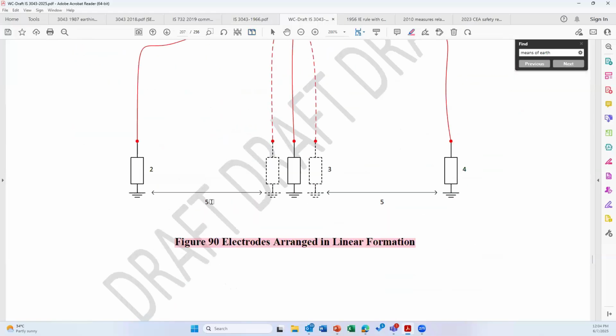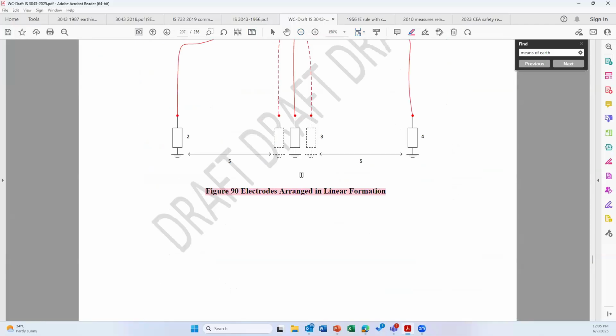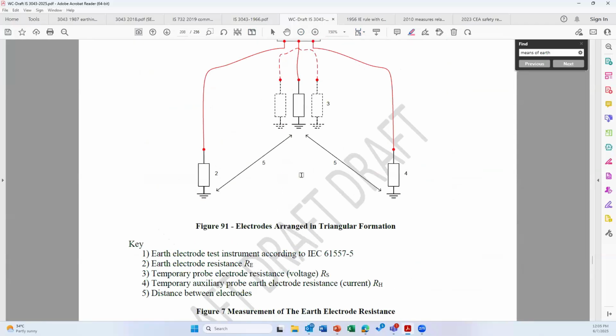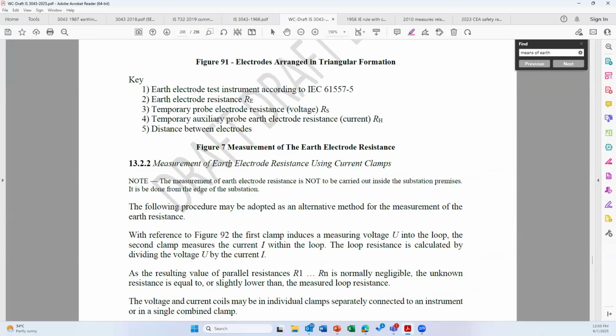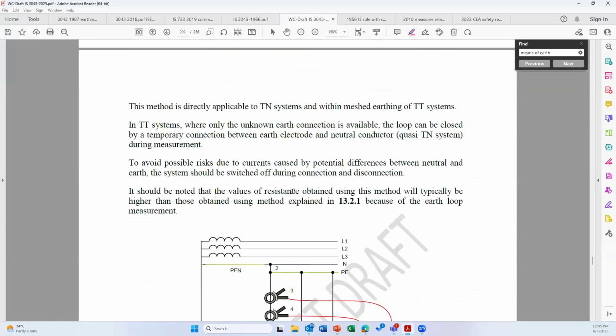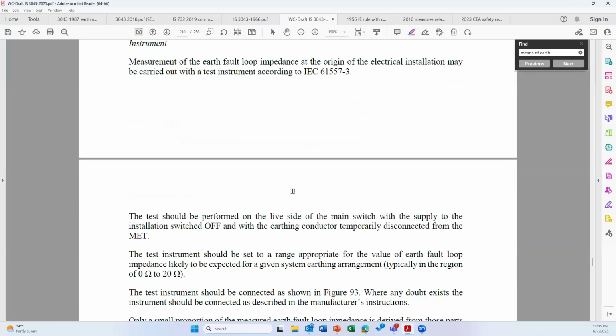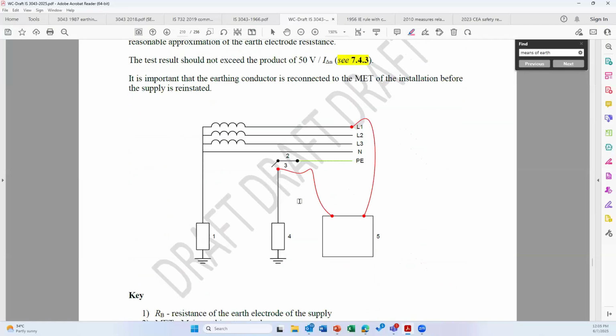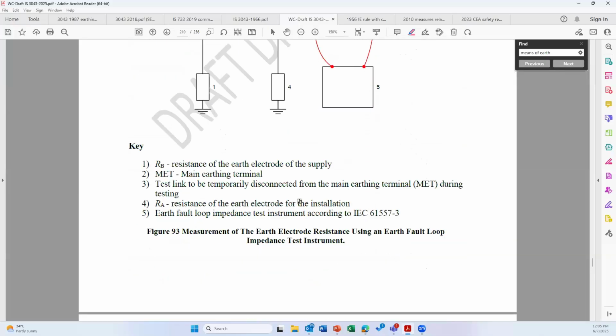Please note that earth electrode resistance measurement is not necessary always. It may be required if you go for a type A earth electrode for a lightning protection system. In other cases, it's not mandatory. However, the figures are included. The earth electrode resistance using current clamps is included with pictures. The earth electrode resistance with the help of a fault loop impedance meter has also been included.